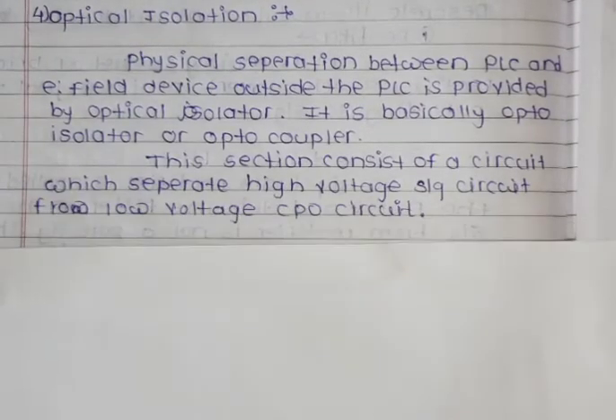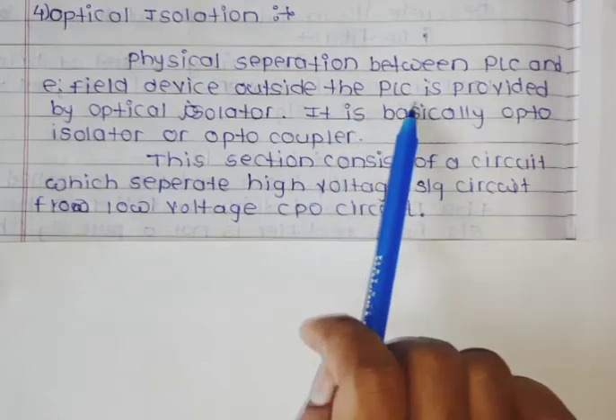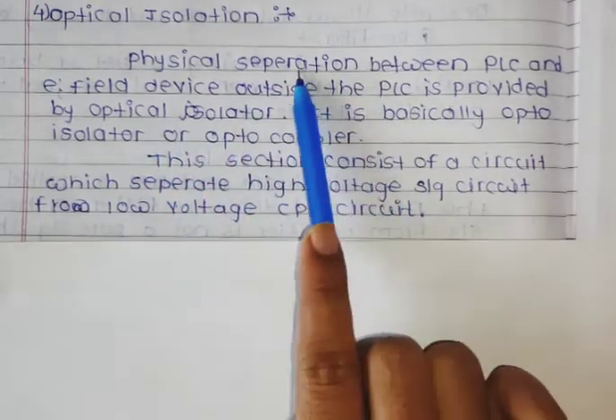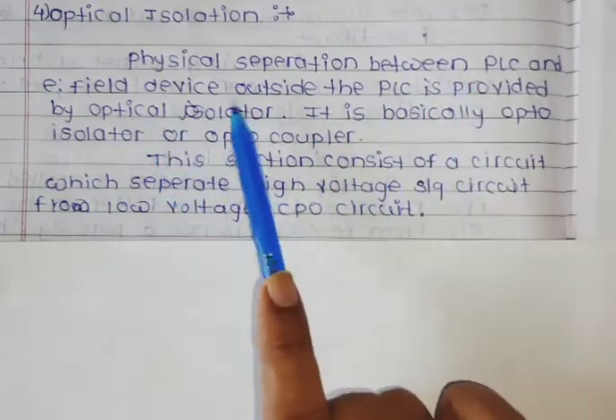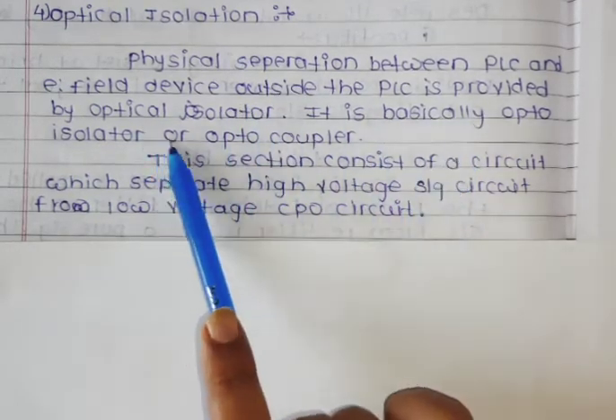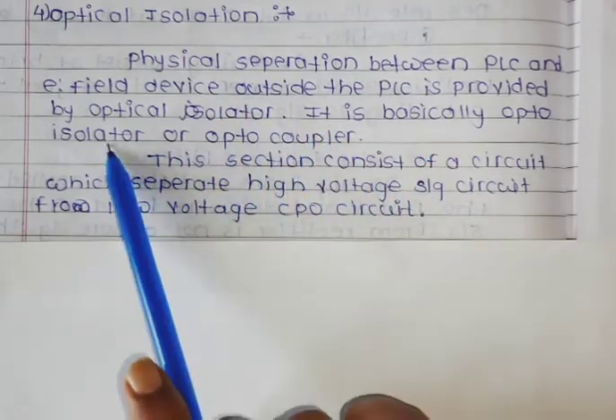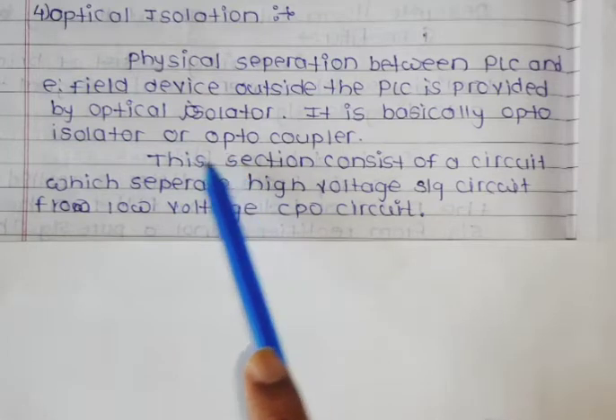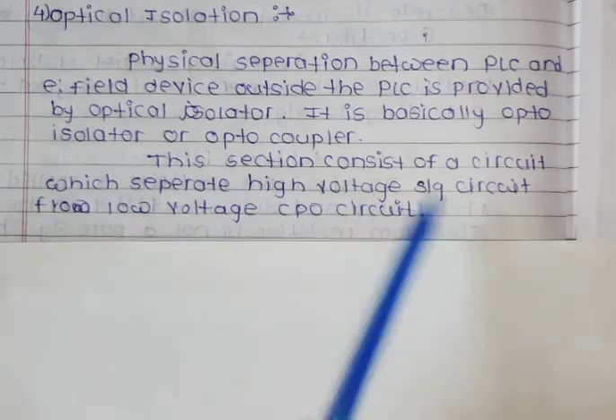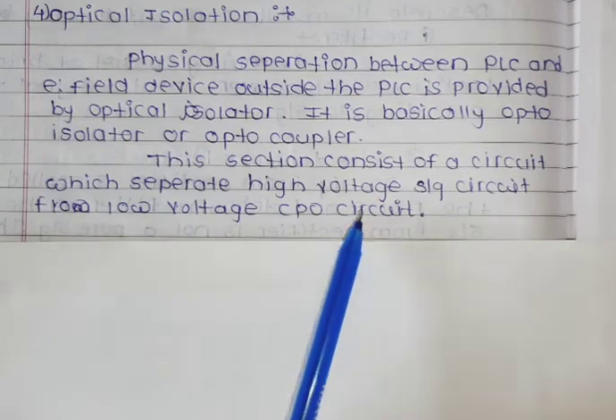After that, we see optical isolation. The physical separation between the PLC and the field device outside the PLC is provided by the optical isolator. It is basically an opto-isolator or opto-coupler — both are the same. This section consists of a circuit which separates the high voltage signal circuit from the low voltage CPU circuit.